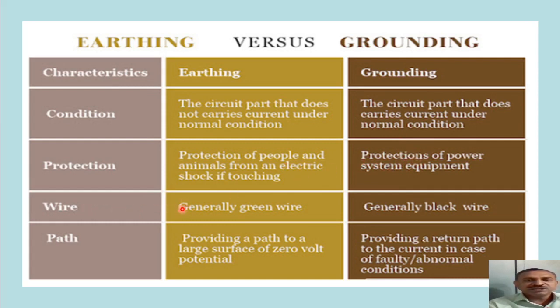The wire that is usually preferred color wise is the green wire for earthing and black wire for the grounding. The path that is done in earthing for a current is providing a path to a large surface of 0 volt potential, and in grounding we are providing a return path to the current in case of faulty or abnormal conditions. So in grounding we are providing a return path, thereby we will be able to detect that fault current and breaker will trip and that equipment will be saved from any further damage.